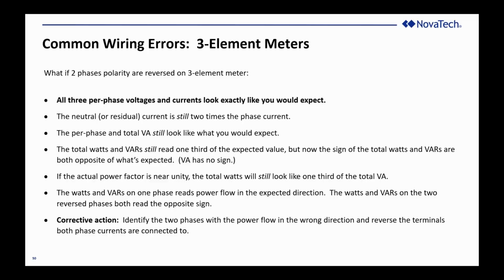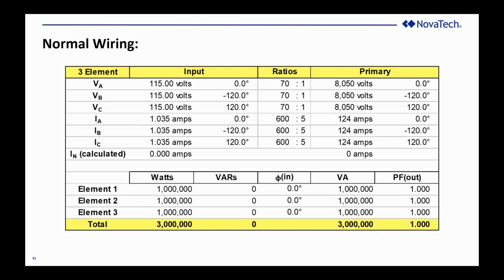The watts and VARs on the one phase will read in the correct expected direction. The two that are wired wrong will read in the opposite direction. Corrective action, find out which two phases are reversed and correct them.